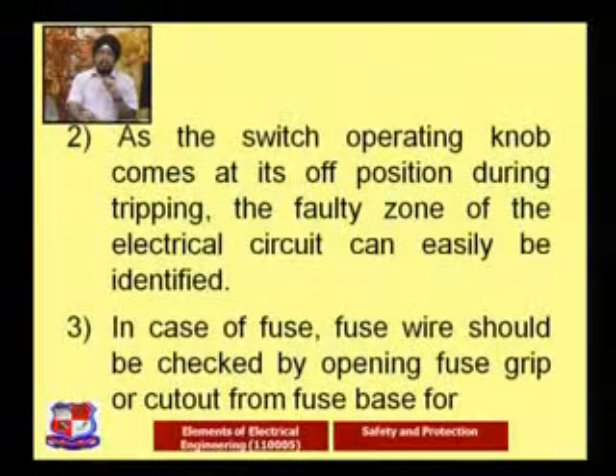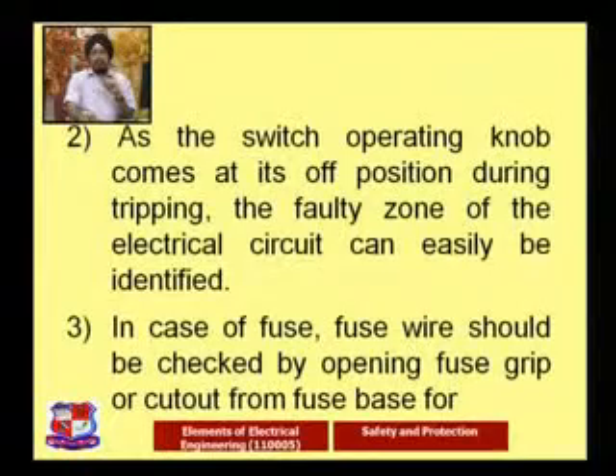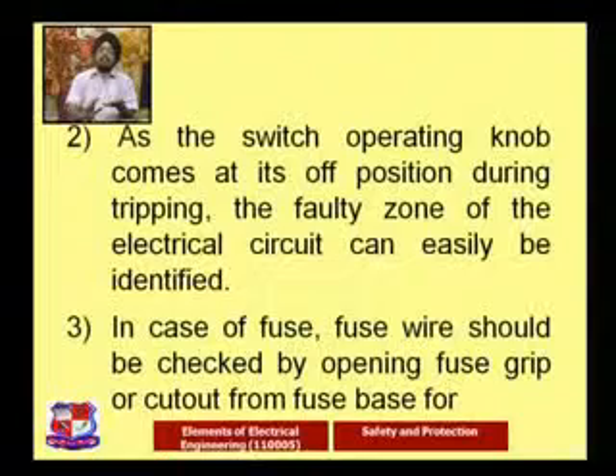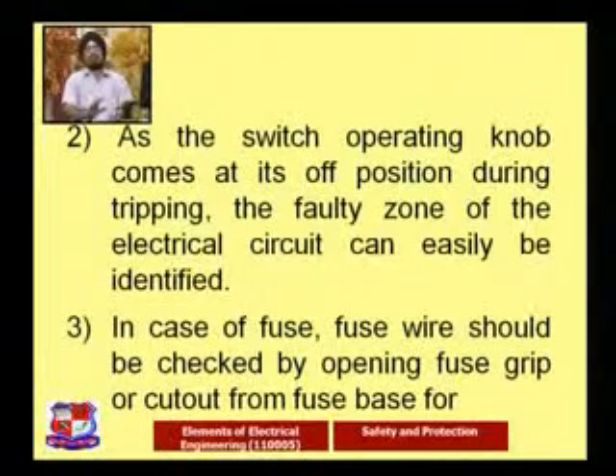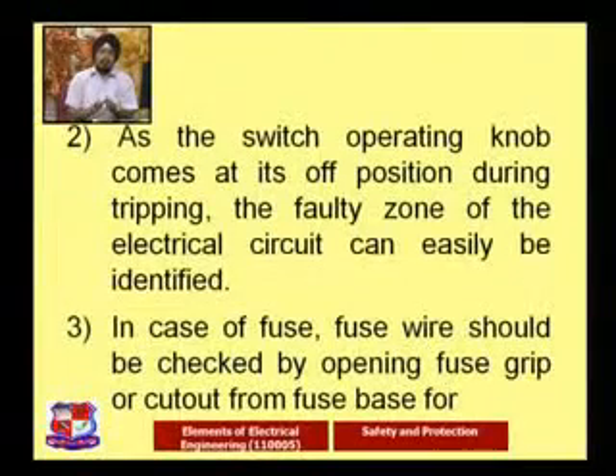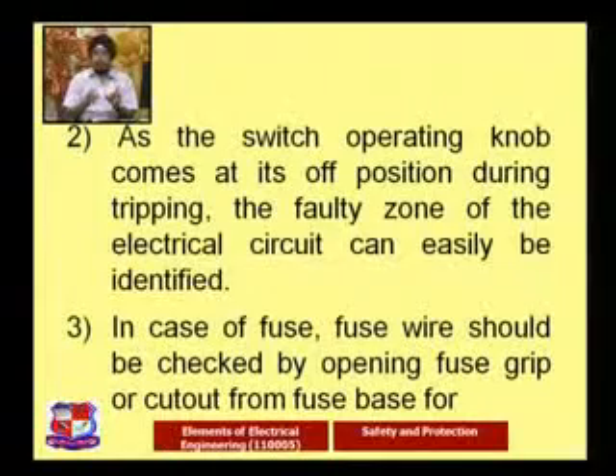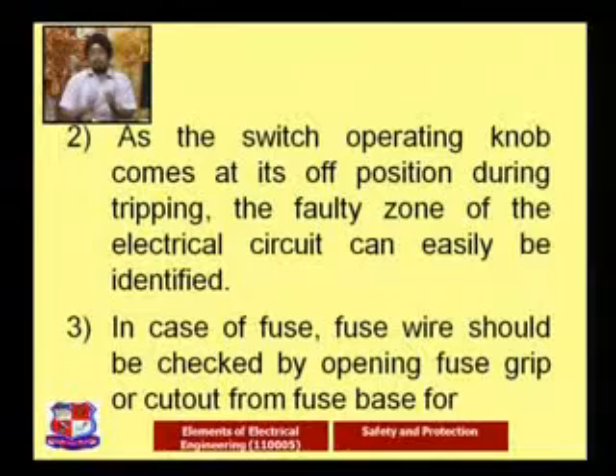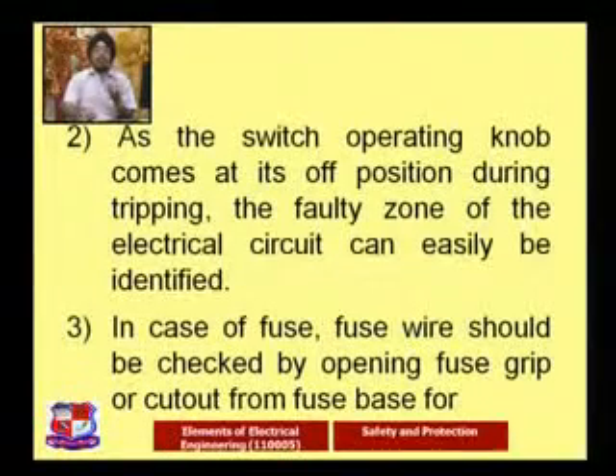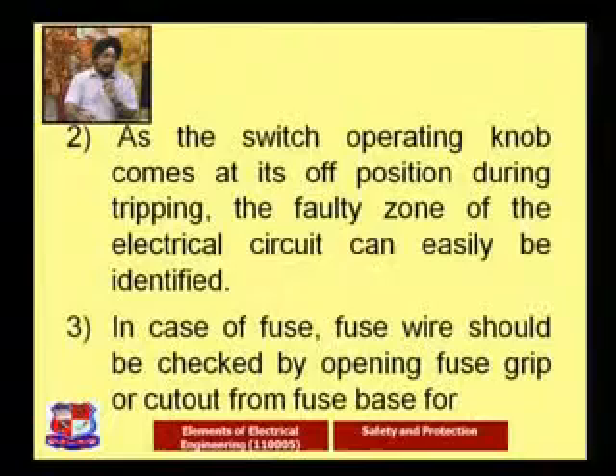As the switch operating knob comes to its off position during tripping, the faulty zone of the electrical circuit can be easily identified just by looking at the circuit. We can say right now this MCB is tripped, so this zone might have a fault. But in the case of a fuse, we have to check each and every fuse. We have to take that particular fuse out and check whether the fuse has burnt out. If it is okay, let's insert it back. If it is not proper, meaning the wire has melted, let's rewire it. So in that way the convenience is there.